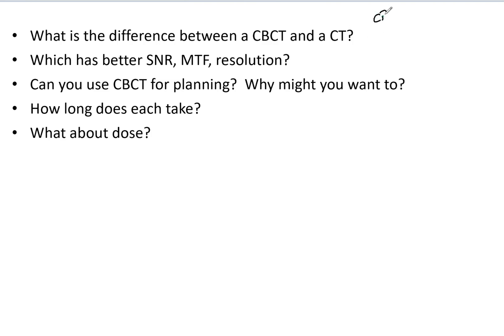Starting with cone beam CT: based on the name, it uses a cone-shaped x-ray beam, whereas a standard CT uses a fan beam — specifically diagnostic CTs. A normal CT has a very high output with a rotating anode x-ray tube, whereas the cone beam CT has a much lower powered fluoroscopy tube.